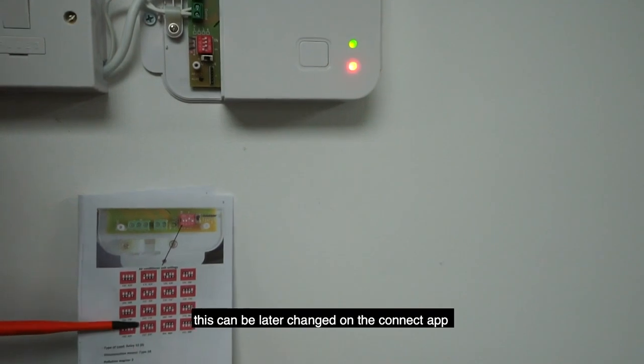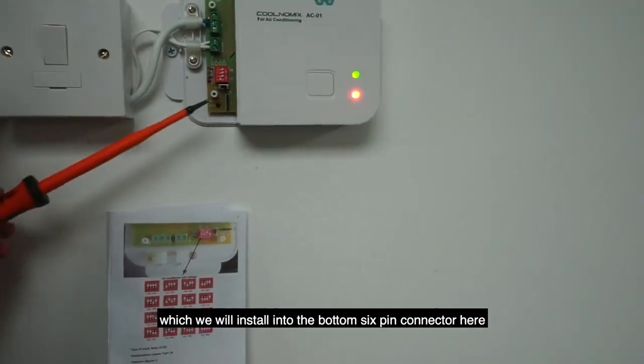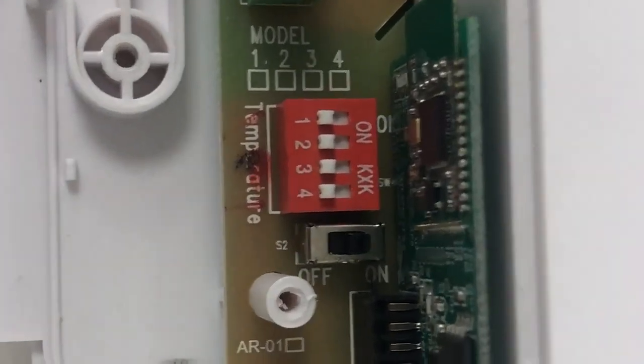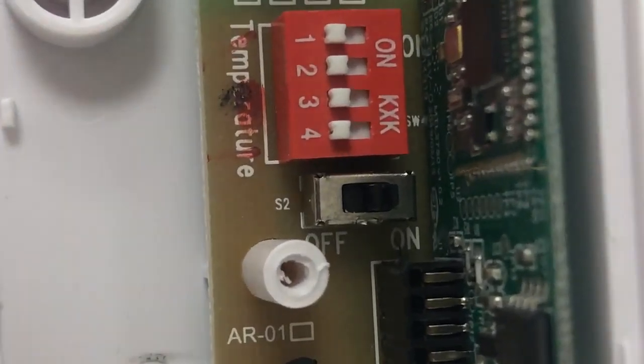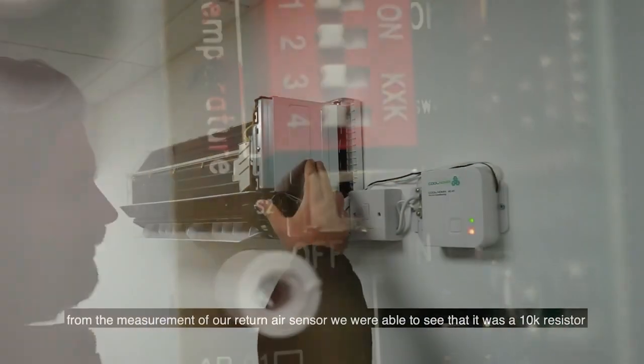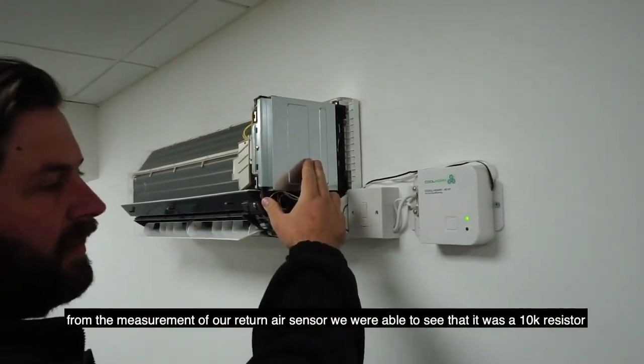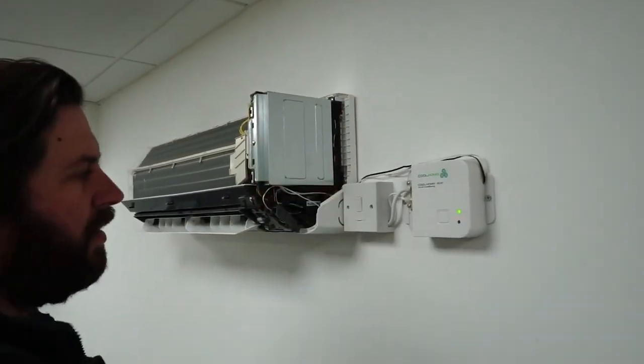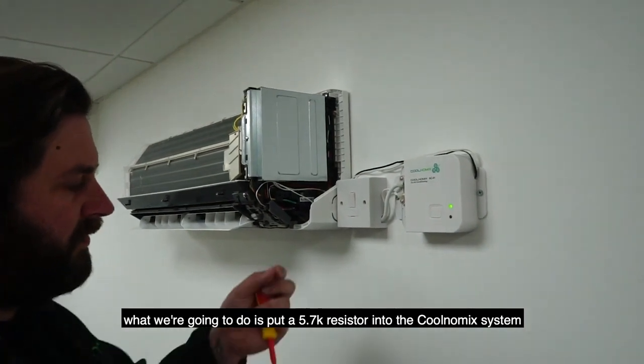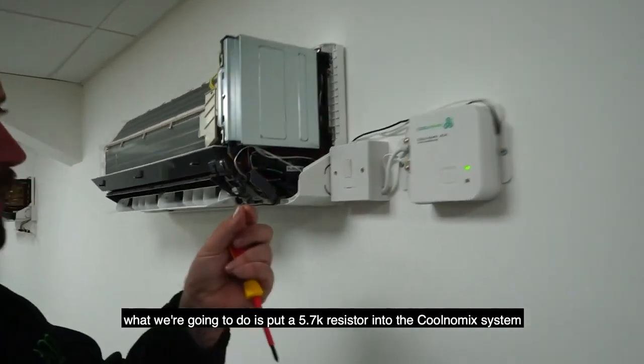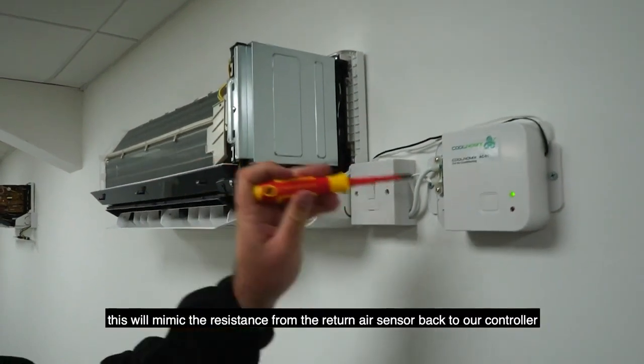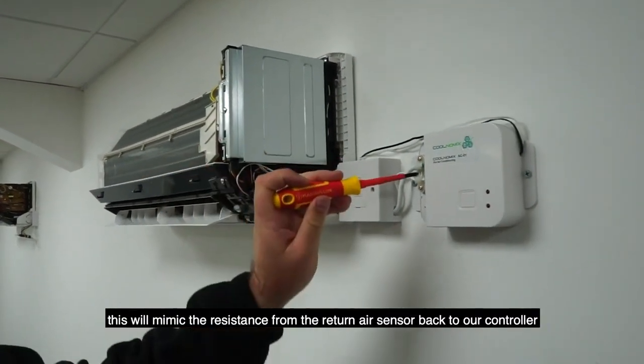This can be later changed on the Connect app, which we'll install into the bottom 6-pin connector here and connect via our phone on an Android system. We can do that later on. From the measurement of our return air sensor, we were able to see that it was a 10k resistor. What we're going to do is put a 5.7k resistor into the Coolnomix system. This will mimic the resistance from the return air sensor back to our controller.